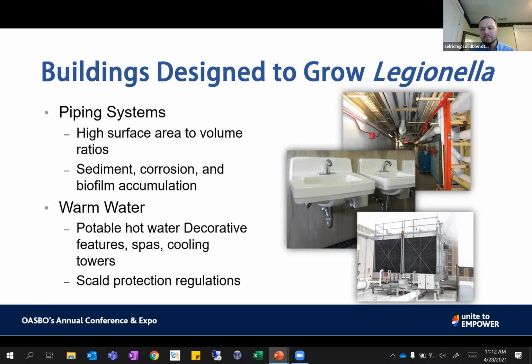And when you maintain it below 120, let's say 110 to 120, that's actually a great temperature for the bacteria to continue to grow and reproduce. So some of the things that we have in place for protection of other items like scald and burn allow this bacteria the opportunity to thrive. Cooling towers, same thing. Most HVAC cooling towers are going to be operating around 90 to 100 degrees Fahrenheit, which is an ideal temperature for that bacteria. Decorative water features, spas, those types of things as well. So temperature plays a big role in this bacteria, and that's one of the issues with building design.